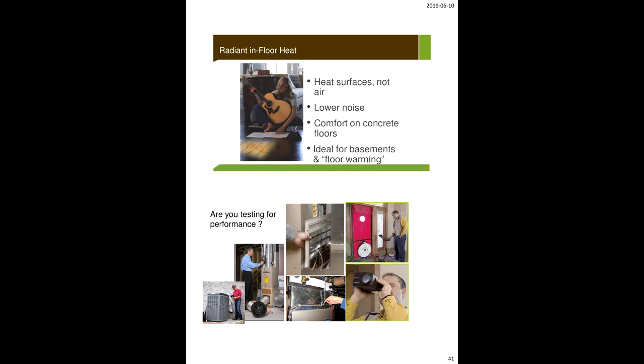The other thing is testing. Again, if you haven't done testing, I'm not just talking blower door—I'm going to show you these other things on the mechanical side: testing static pressure in your system. It takes all of 5 minutes for somebody to check the static pressure in a forced air system. If you don't have enough static pressure, you don't have enough gas in the tank to push the air through the rest of the house. It's the single biggest issue we're finding in the field.